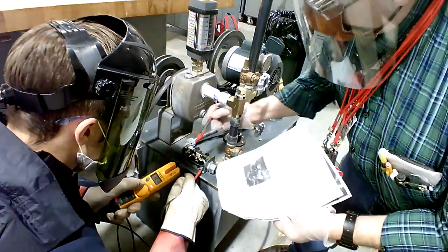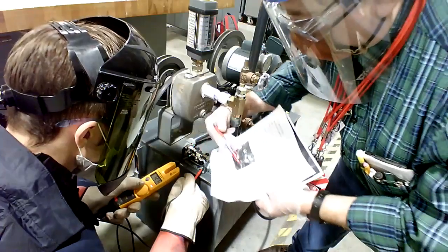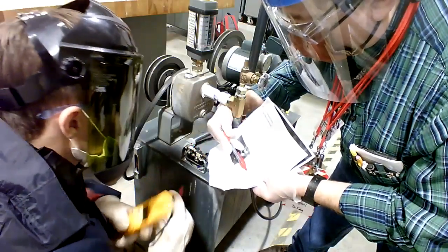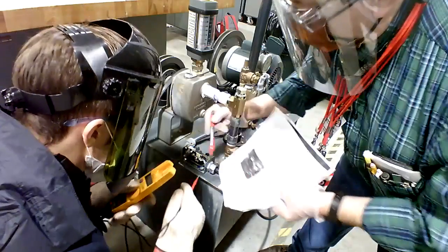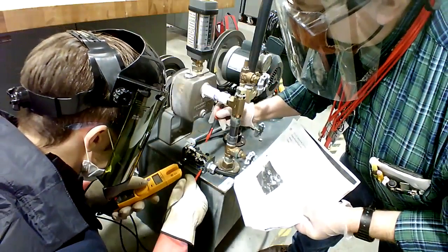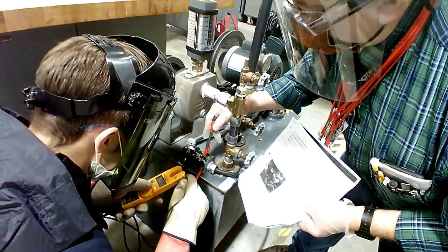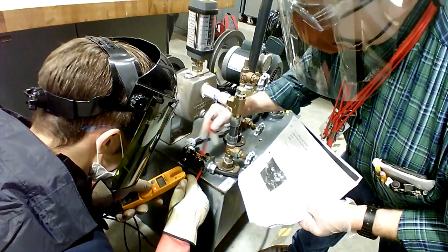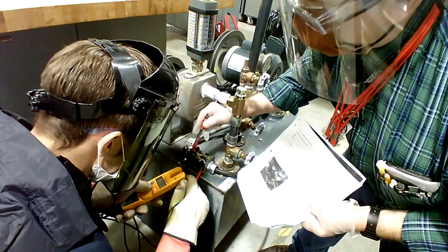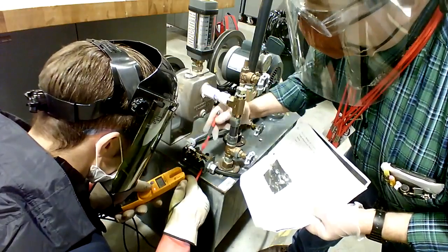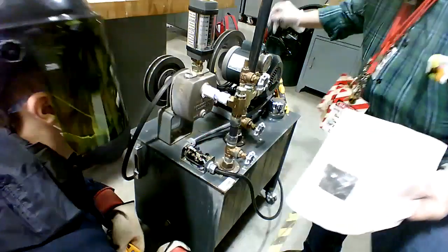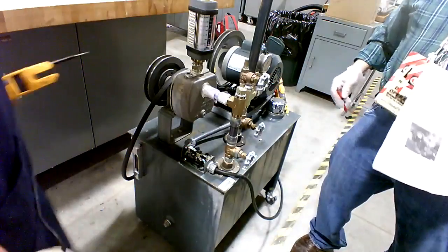Now, go another step. Go from where it leaves the switch going into the overload and check it leaving the overload. Right there. Where it leaves. And that's where it goes to the motor. And you know that the overload's good, the switch is good, and there's nothing wrong in here, right? And that's where it goes out. That's where it comes into the motor over here. Now cut it back off again.